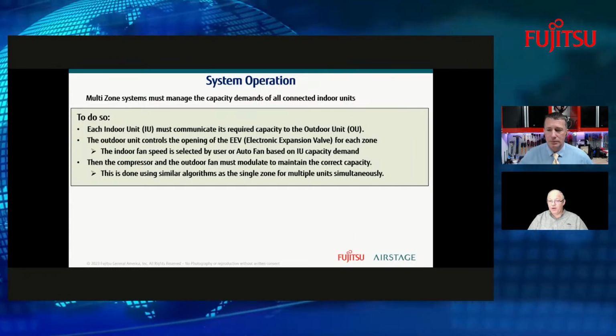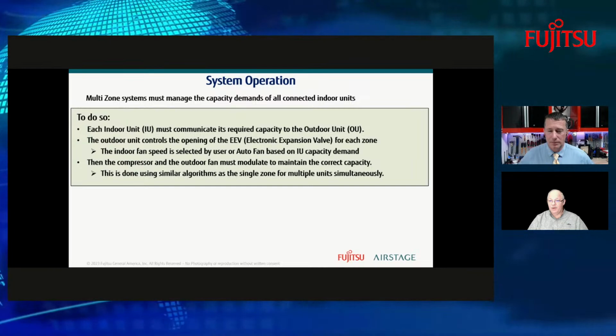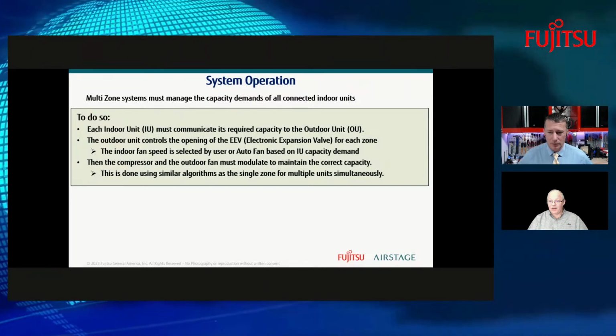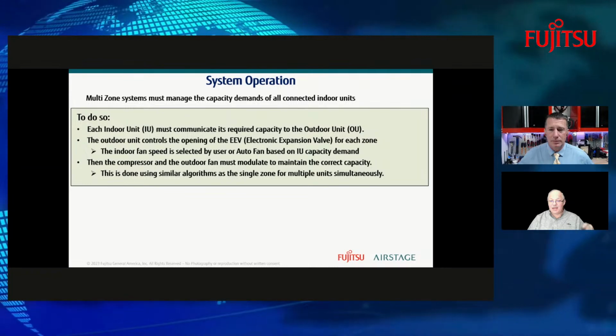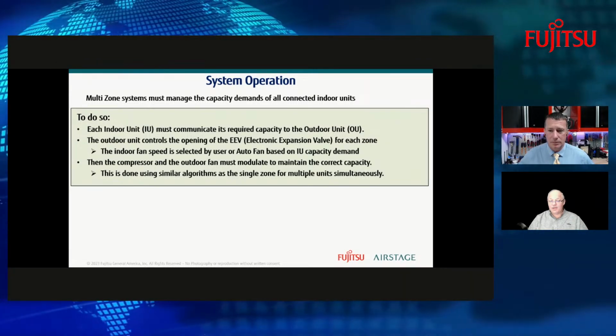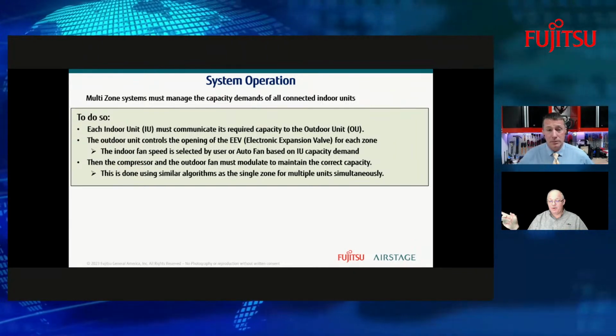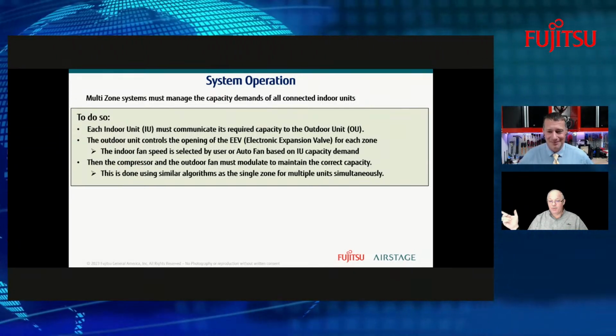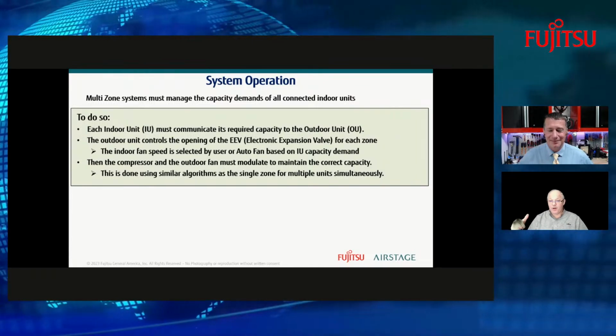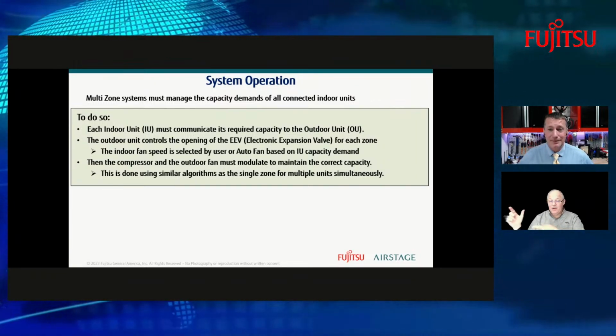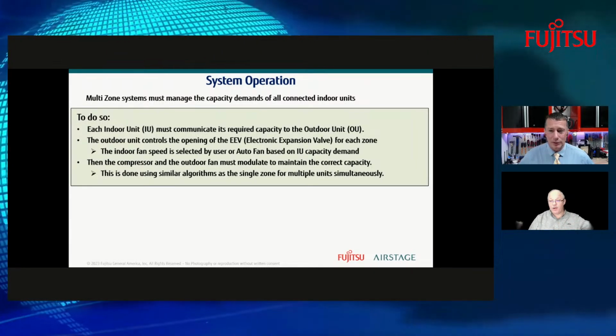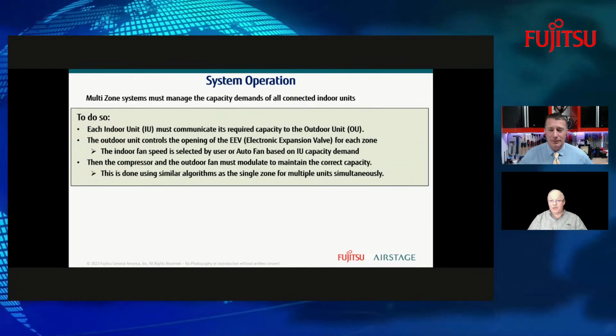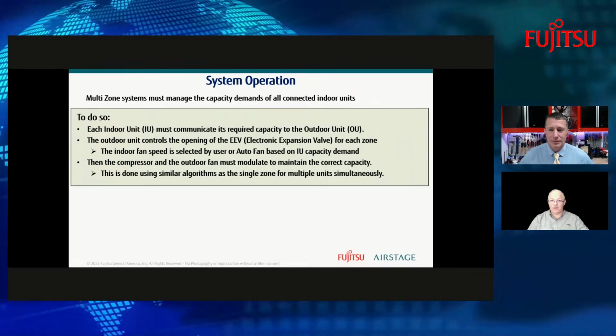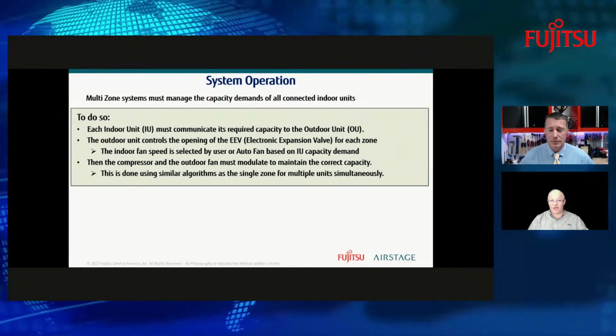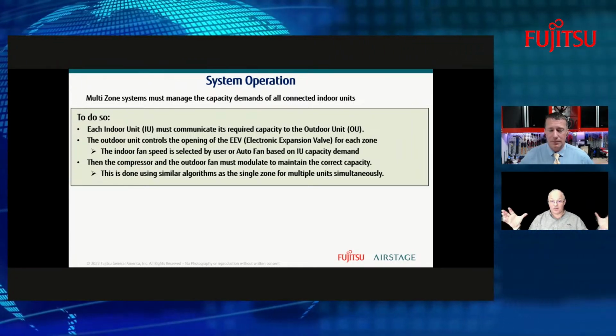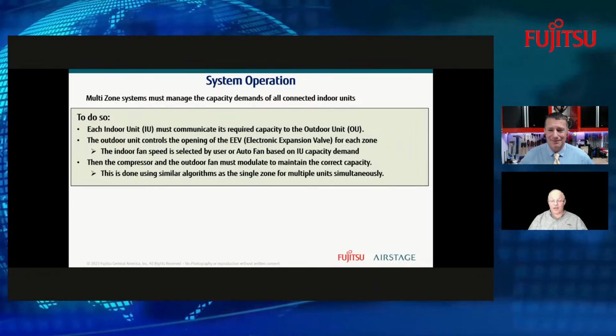Now, just because the compressor and the fan outside have to ramp up because you've got 2 or 3 indoor heads now calling, it's not a problem, because the EEV and the outdoor unit is going to tell the indoor unit, well, you need to speed up your indoor fan motor because you're monitoring your own temperature there, and I'm sending you a certain amount of refrigerant on this EEV to you. That indoor head doesn't care what's going on with any other indoor head. It just knows what it needs. So the system is getting all this information from all these thermistors, from all these indoor units, and it's looking at what's happening with all these indoor units collectively. And it says, I now have a third one that kicked in.